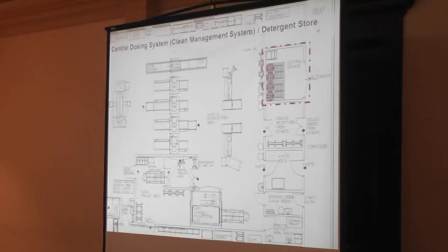In Sweden we even have the service technician go out to the customer, and he checks the detergent. He can do that by mobile phone and check the level. And he can see on Friday before the weekend, I really don't want to go away to the university to change. So he checks on Friday, oh, I need to go out, and he changes that for them. So the CSSD really doesn't want to do that changing of detergents. So that is also a possibility.